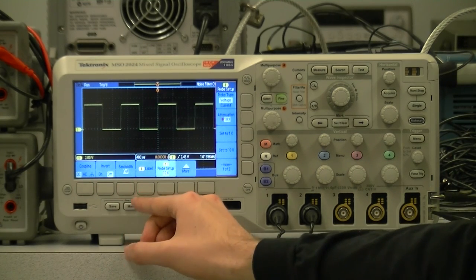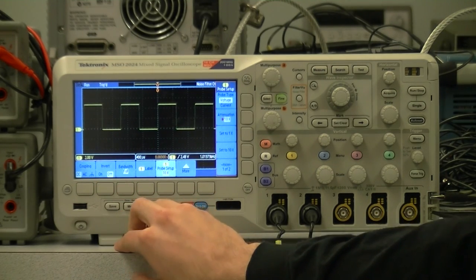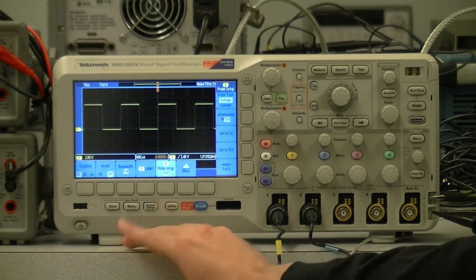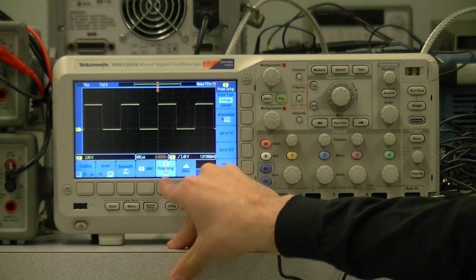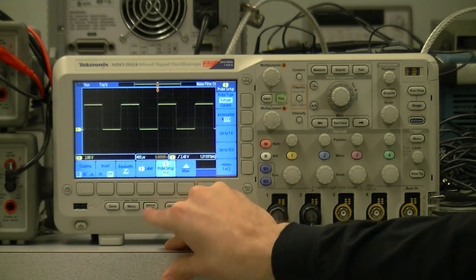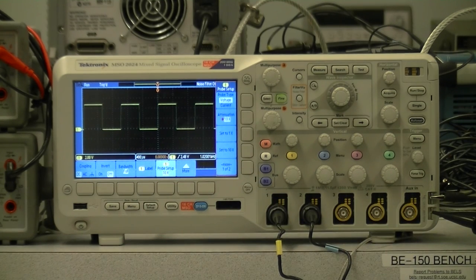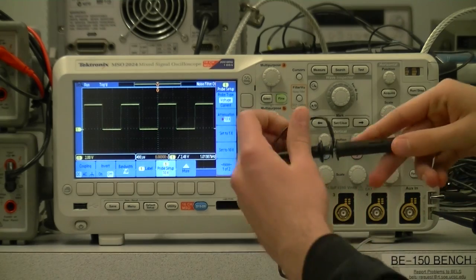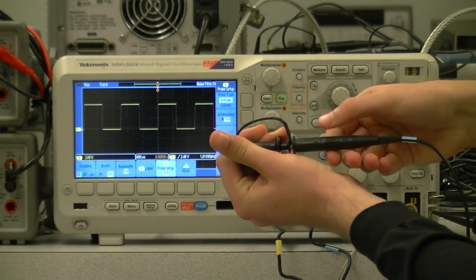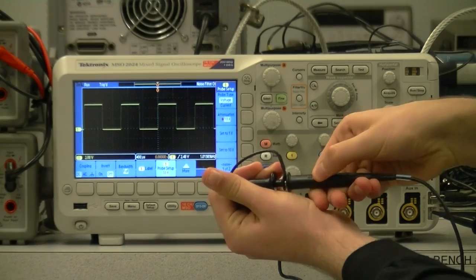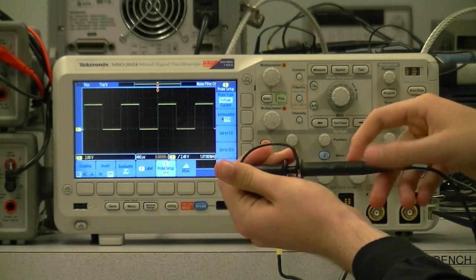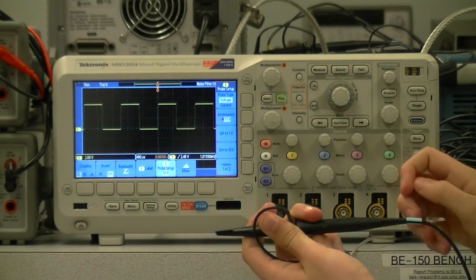The bandwidth and label options similarly aren't very important for this class. Probe setup, however, this button is very important. It currently shows 10x, and the probe itself has a little slide switch on it, which can be set between 1x and 10x. It's very important that the probe setting match the oscilloscope setting.